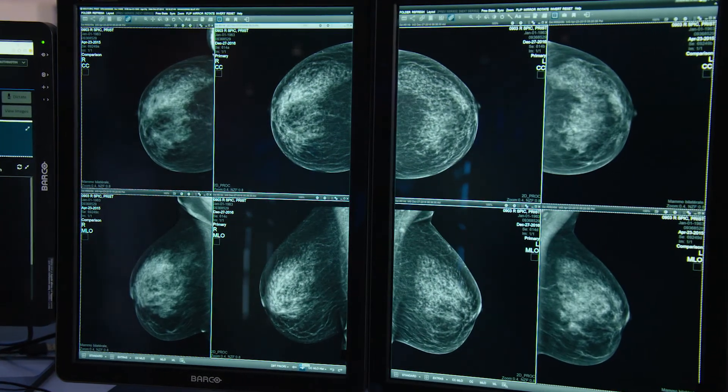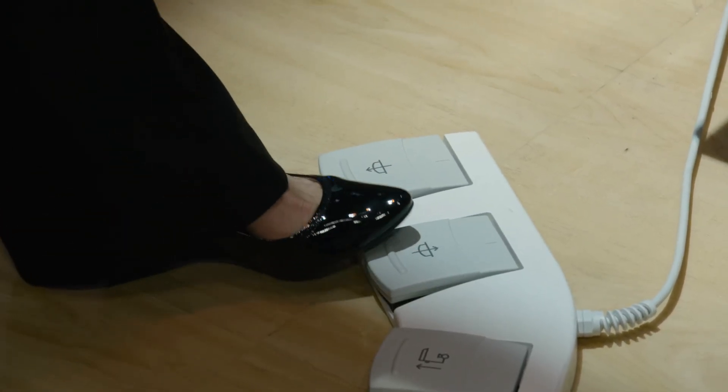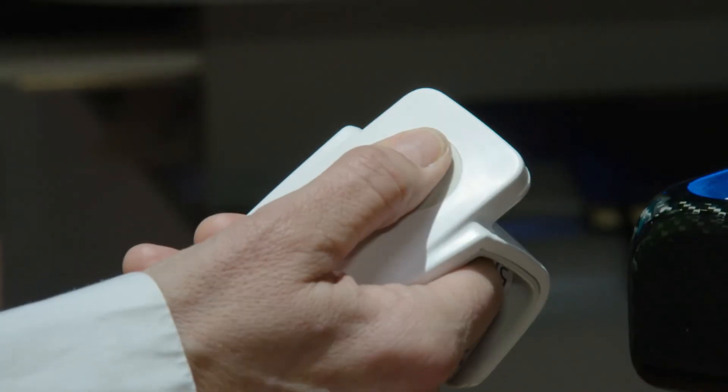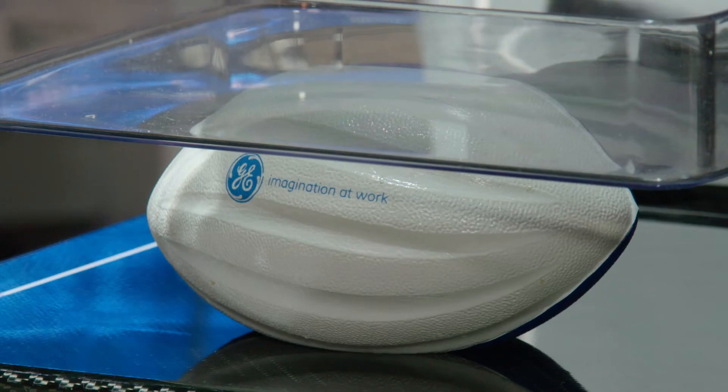With Dueta, I as a patient can now work with my technologist to achieve the most optimal compression. With better compression, the radiologist has better image quality and I as a patient have lower dose. The technologist, however, is always in control — they have the responsibility to get the patient to the most optimal compression — but now I as a patient can add a couple more pounds of pressure.